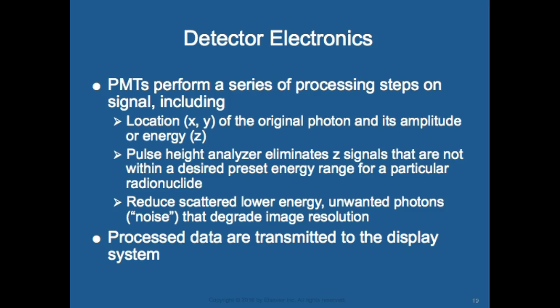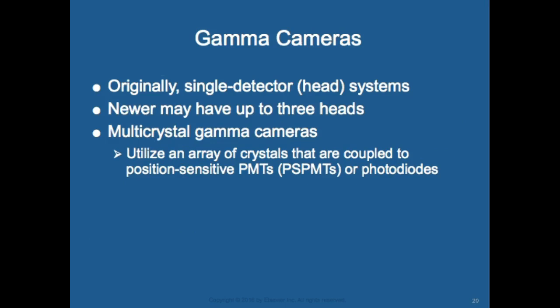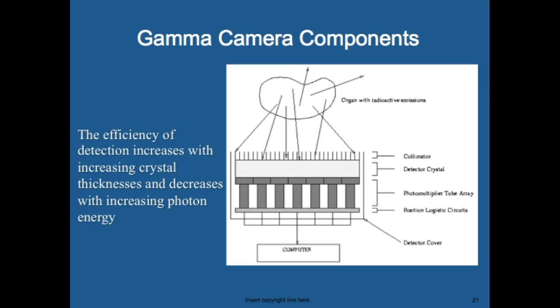The pulse height analyzer acts like a filter, reducing scatter, low energy, and unwanted photons — what we call noise — that degrade image resolution. Processed data are transmitted to the display system. Newer systems may have up to three heads, and multi-crystal gamma cameras utilize an array of crystals coupled to position-sensitive PMTs or photodiodes. The effectiveness of detection increases with increased crystal thickness and decreases with increased photon energy.